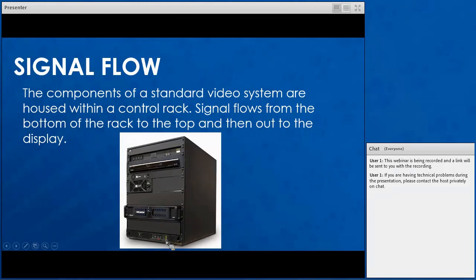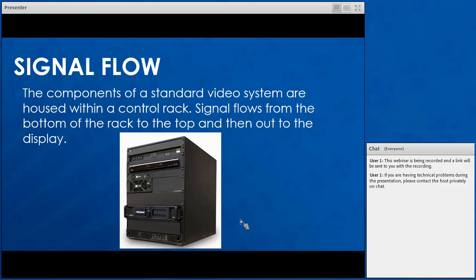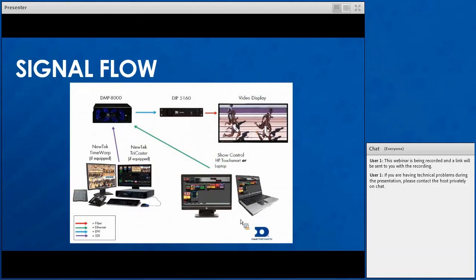Within a control rack you have a UPS, typically a digital media player, and a video image processor. DVD players and tri-casters can be included as well as other video sources. The UPS, located at the bottom of the rack, stands for uninterruptible power supply — think of it as a giant battery for your rack. Its primary purpose is to keep your rack running for a small amount of time should your site lose power. UPSs typically have a 20-minute battery life window once power on your site is lost.